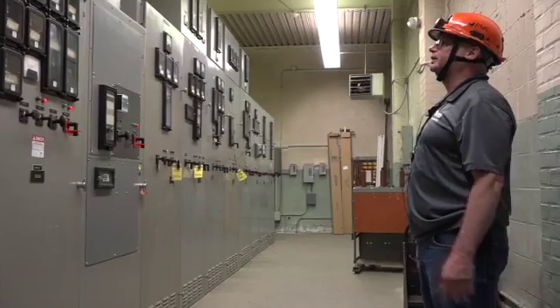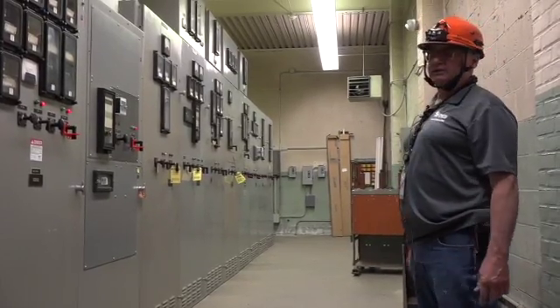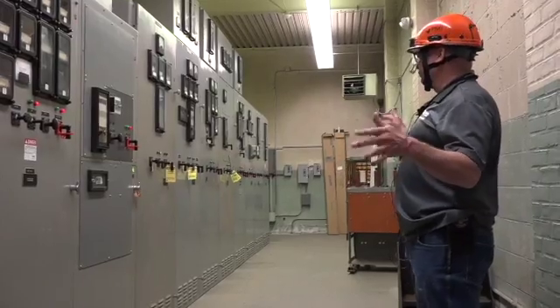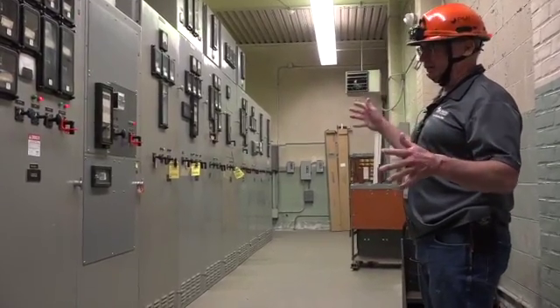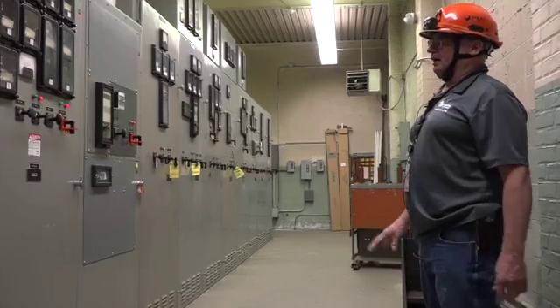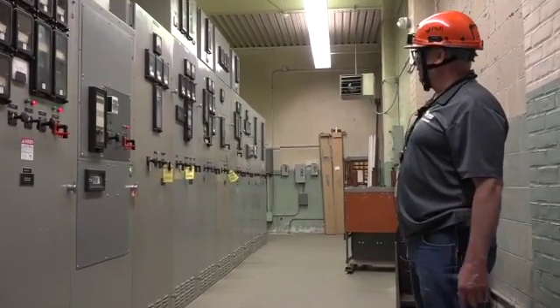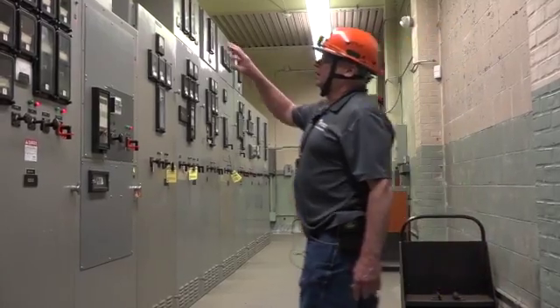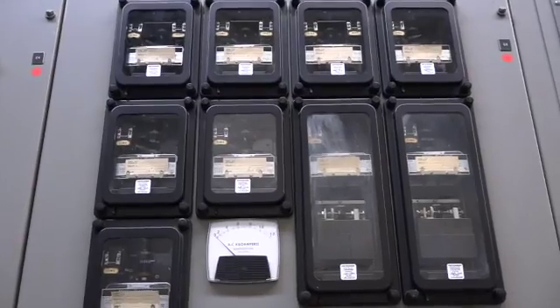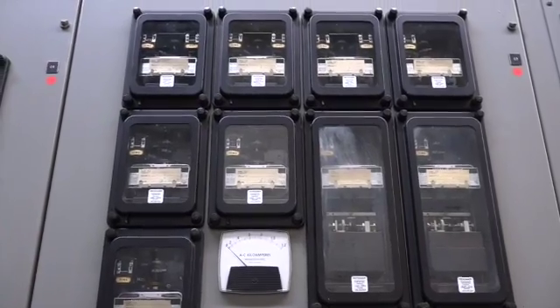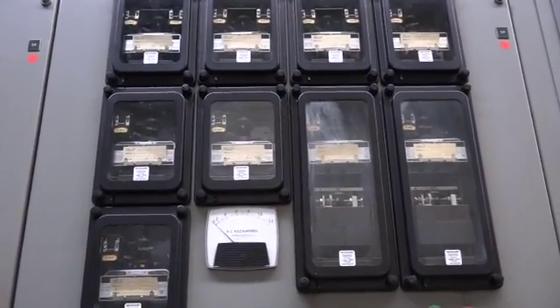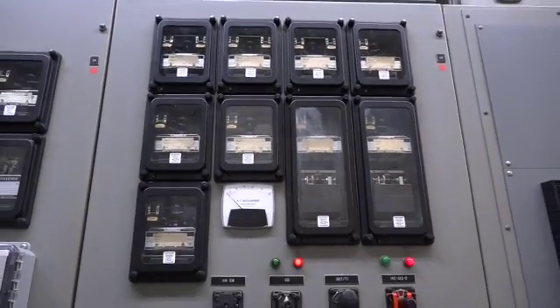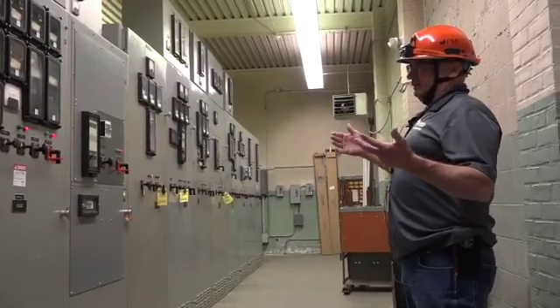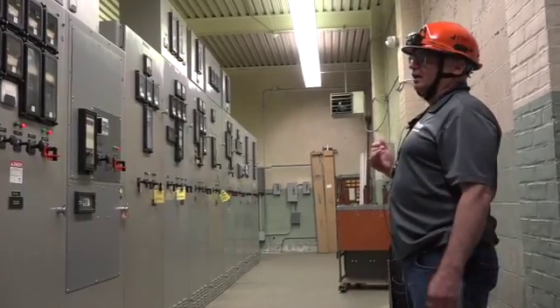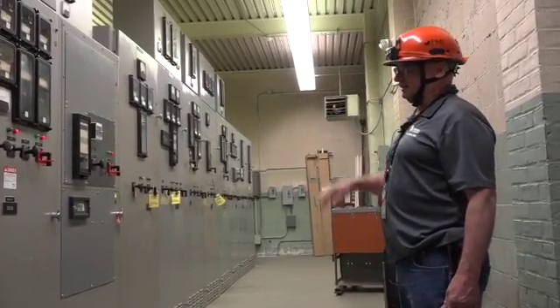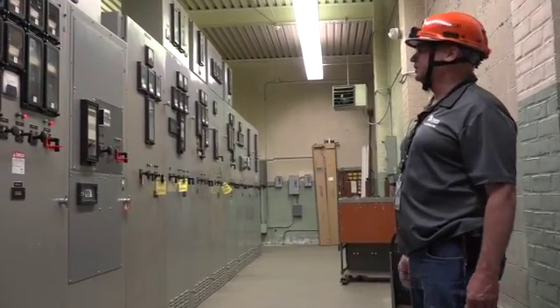This is a typical substation switch gear. It's called metal clad gear. In a lot of utilities' substations, this is old gear. The more modern looks a little bit different, but this is what a substation typically looks like. All these black boxes that are in the doors, those are all the trip relays. They sense the current on the lines going out, and they'll trip the breaker if there's a fault. That's what senses the current and sends the signal to the breaker to switch.